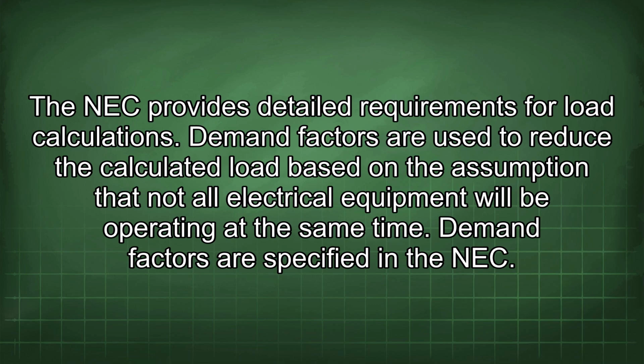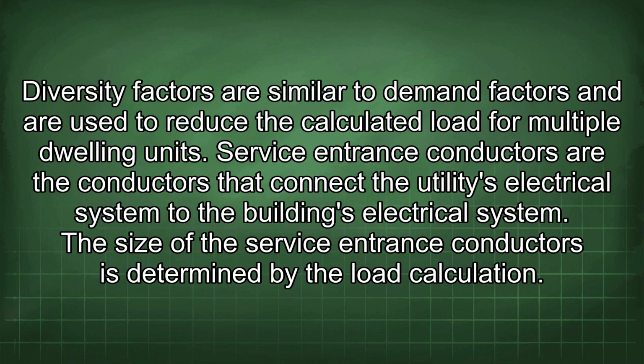Demand factors are used to reduce the calculated load based on the assumption that not all electrical equipment will be operating at the same time. Demand factors are specified in the NEC. Diversity factors are similar to demand factors and are used to reduce the calculated load for multiple dwelling units.